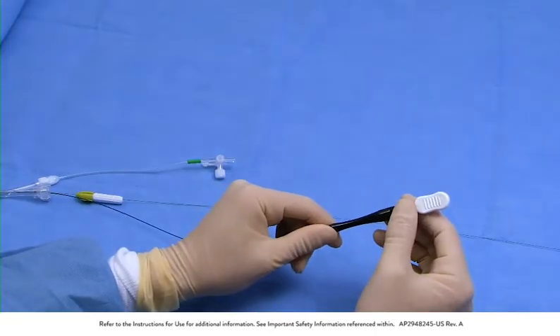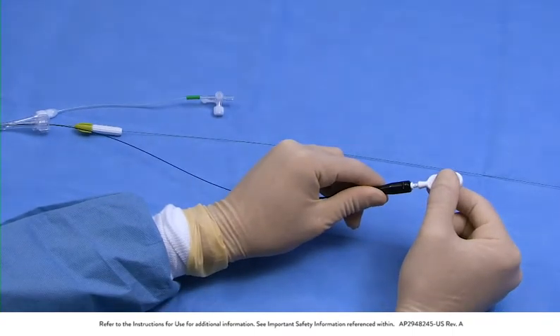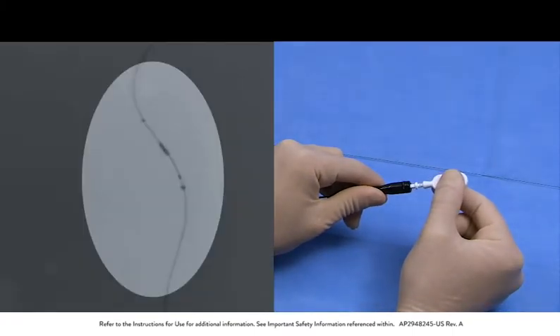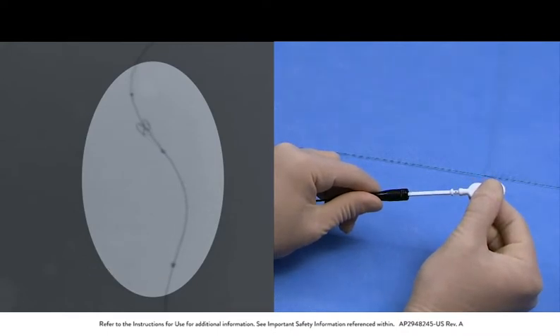Hold the black handle steady and pull back on the white pull handle to deploy the filtration element. Deployment is occurring when the distal marker band on the delivery catheter moves proximally away from the marker bands on the filtration element.